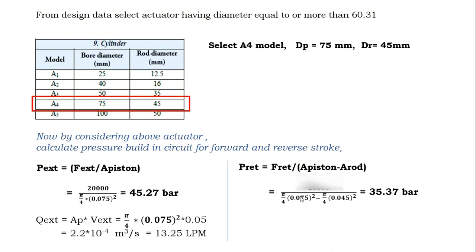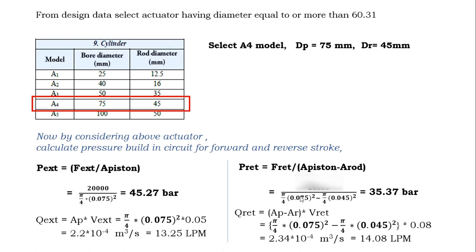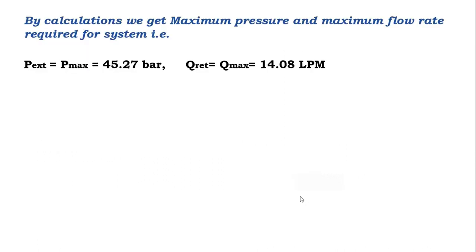Now find the flow rate for extension and for retraction. By calculations, the maximum pressure required for the system is 45.27 bar, which is built at the time of extension, and the maximum flow rate is 14.08 liters per minute, which occurs at the time of retraction. Using these two maximum parameters we proceed to find the other components.